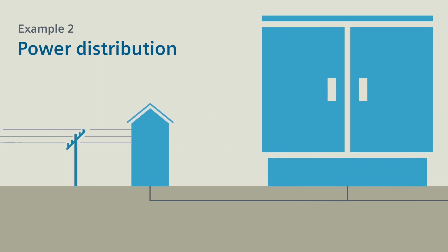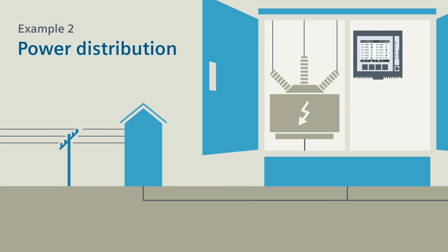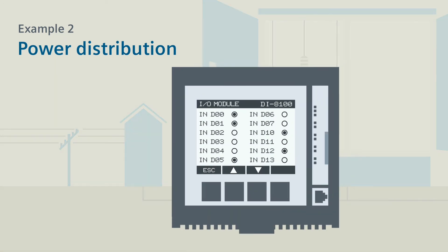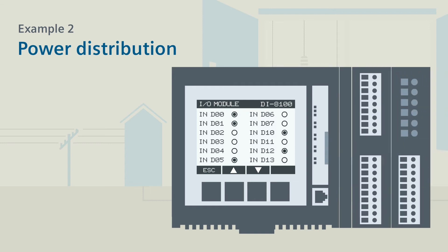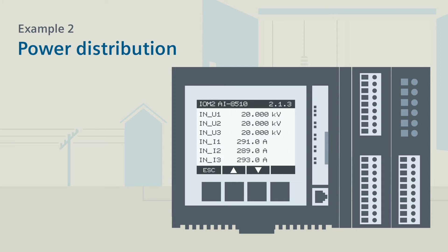Our tip? Use a CP8000 compact device in the secondary substations. The advantage of this solution? You can look at the status indications of the inputs and outputs directly on the device display. If you additionally wish to monitor currents and voltages, simply complement the compact device with the AI8510 and CM8820 I/O modules.